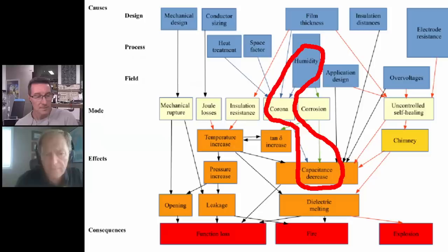And the darker blotches are likely a result of end termination corona type effects, something on that order. So it's always difficult to comment, maybe 15, 20,000 miles away or so, and not having dealt with the parts. But I think that's pretty much the scenario. It's definitely a moisture event.